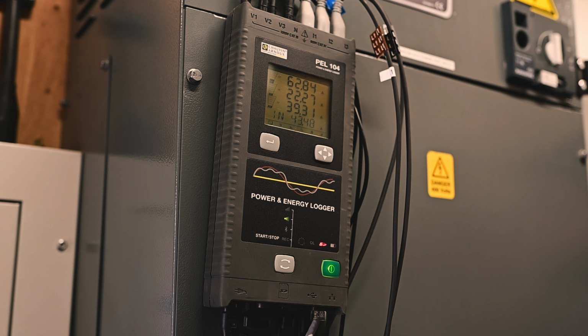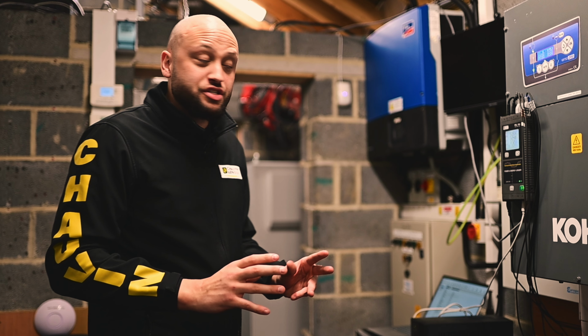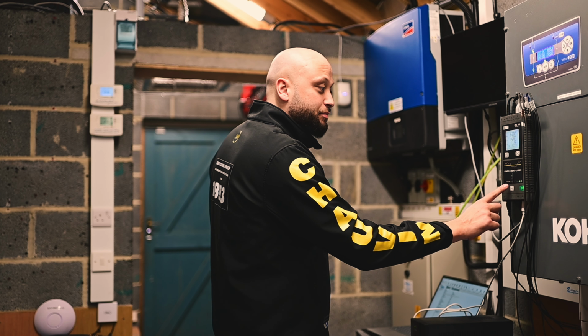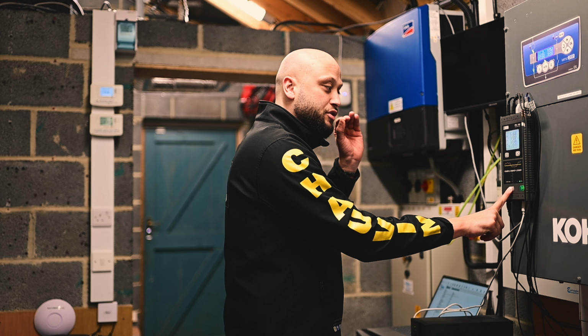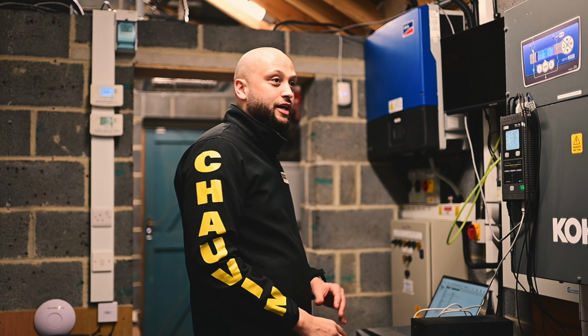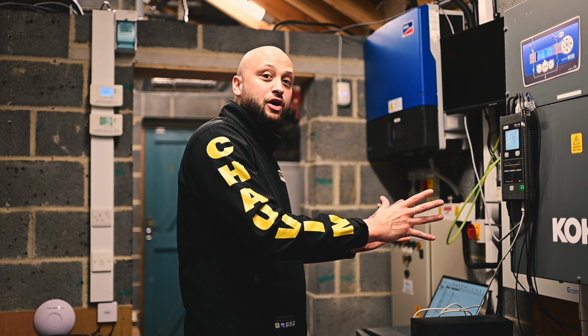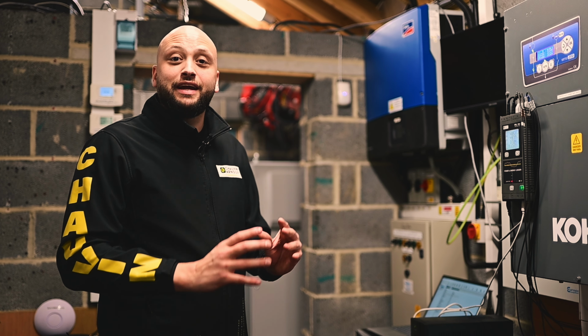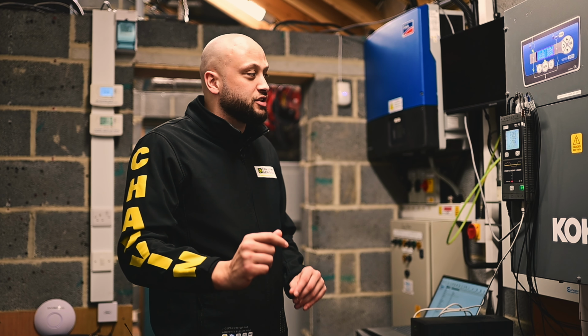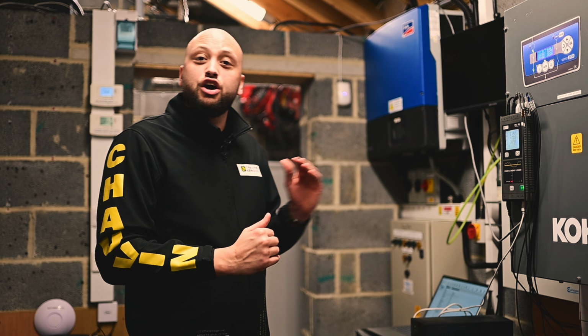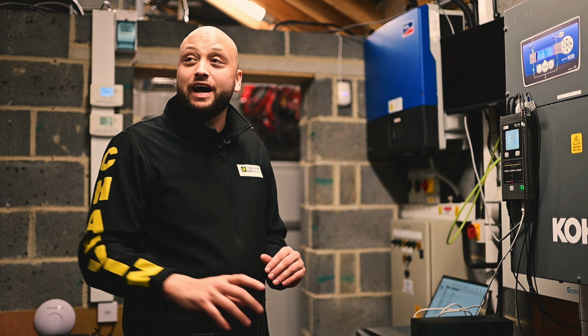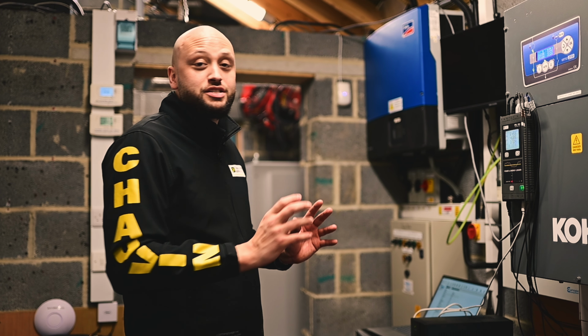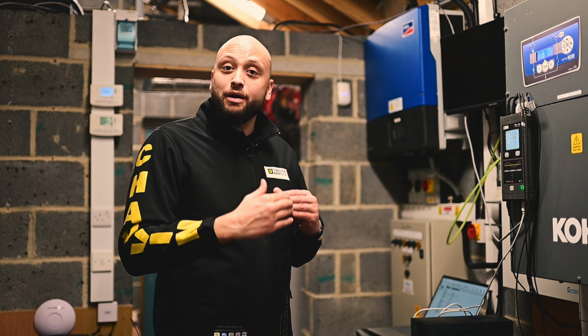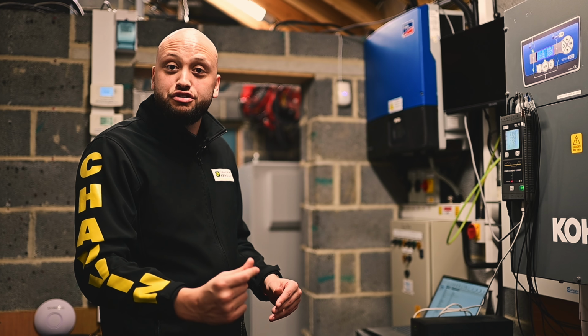As you can see, we've already connected the CTs and the voltage connections. We're going to get it started by pressing and holding this button, waiting for the record light to light up, and letting go. The reason we're setting a PEL up here is because we've configured it to send out automatic alarms for the site, just in case it goes over voltage or under voltage. Not only that, if it exceeds the actual fuse and isolator supply rating, we'll be able to capture that data, and it will send a notification to your email.